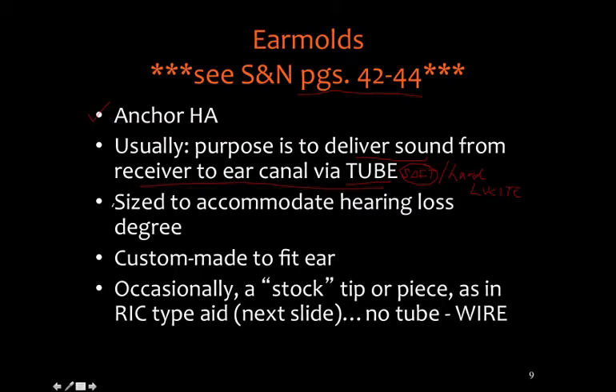The ear molds themselves, there is some logic to the size and other characteristics of the ear mold that could enhance the fitting. Again, one of the other interesting cycles back and forth is, as technology increases, the level of interest in ear molds decreases. Going the other way, when technology is relatively flat, there's interest in ear molds because that's another way to enhance the signal. Another way to think about it is that the acoustic output of the hearing aid, whatever it is, as good as it may be, still has to run through the coupler. And so the coupler, whether it's an ear mold or just the acoustics of an ear canal in the ear type of fitting, we always refer to it as the final filter. So no matter what the hearing aid is doing, it still has to run through that final coupler.